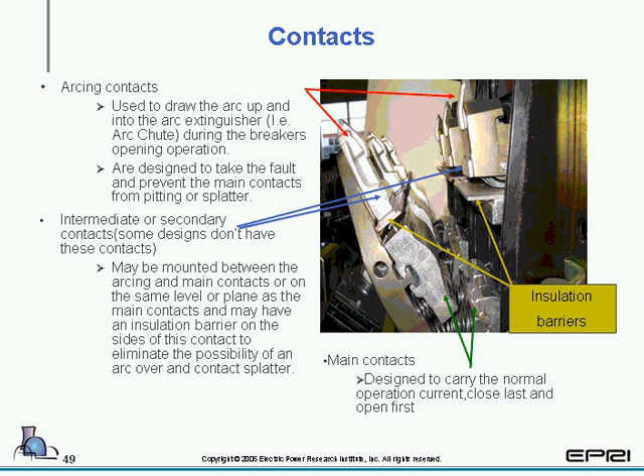Contacts. The arcing contacts are used to draw the arc up and into the arc extinguisher during the breaker opening operations. They are designed to take the fault and prevent the main contacts from pitting and splatter. Some particular designs have an intermediate arcing contact, and you'll see in this particular breaker, this is a DB50, that they are part of the arcing contact structure. But you also may find that the intermediate arcing could be part of the main contacts. And if so, they normally have an insulator barrier on each side of the contact to eliminate the possibility of arc over and contact splatter.